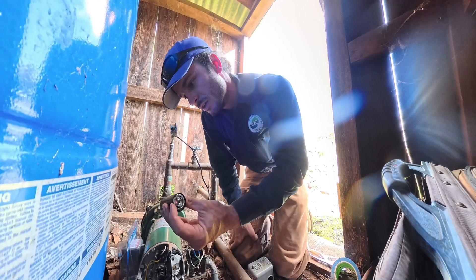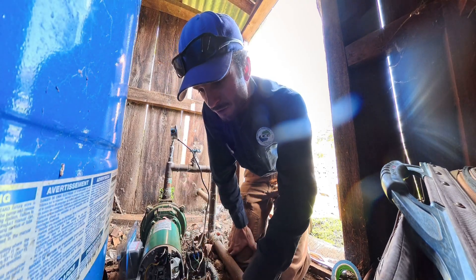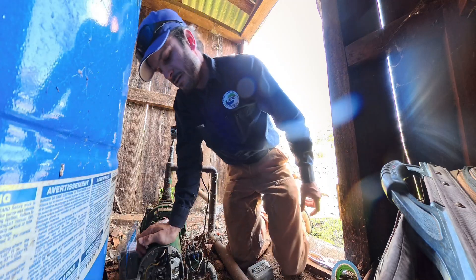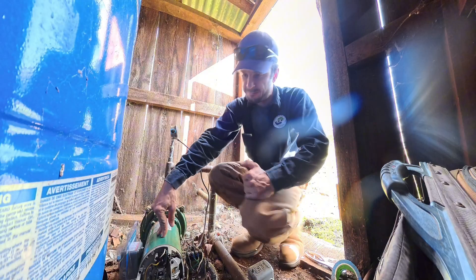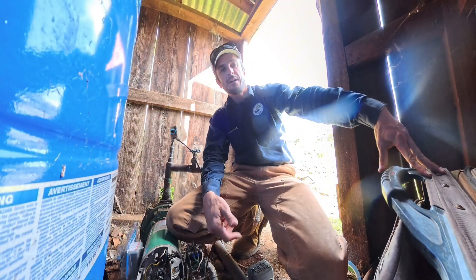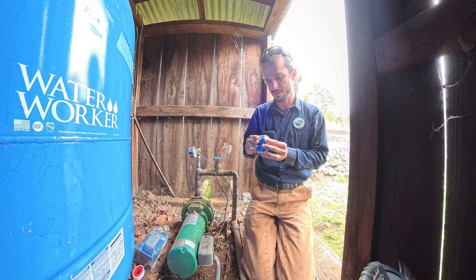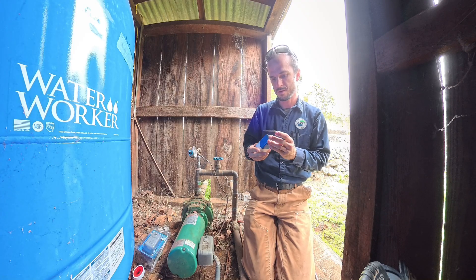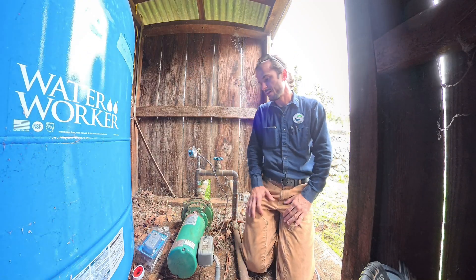Capacitor is toast — we need a new 160 to 193 microfarad. We'll just bring that downtown and next time we're up-country we'll throw it in. Alright guys, we'll see you when we come back to make the repair. Hey guys, so we're back — got our replacement capacitor, brand new. We'll throw it in and see if we can get this thing running again.